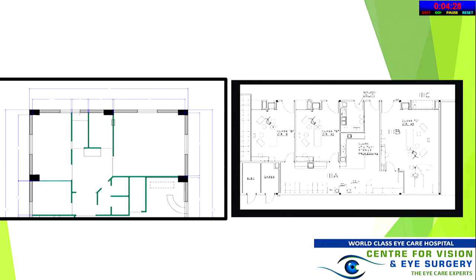Now, this is a single operation theater. This is just an enlarged view of what I was talking about. That is, you have your ward on this side, the patient comes in, this is your cleaning areas, this is your sterile operation theater areas. If you have multiple operation theaters, if you're building a facility with 2 or 3 operation theaters, make sure your corridors are fairly well connected, so that you have a central sterilization which can supply the sterile instruments to both the operation theaters at the same time.